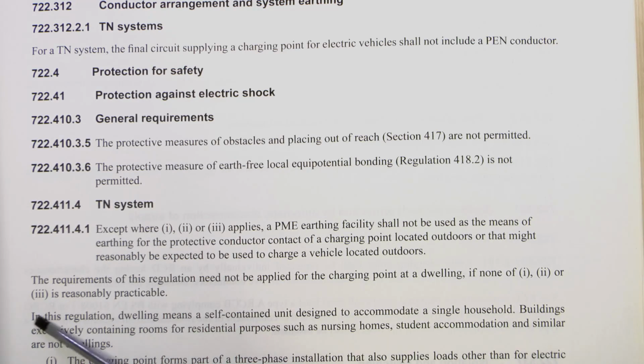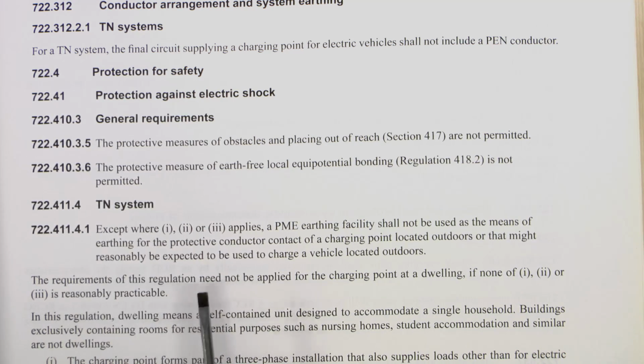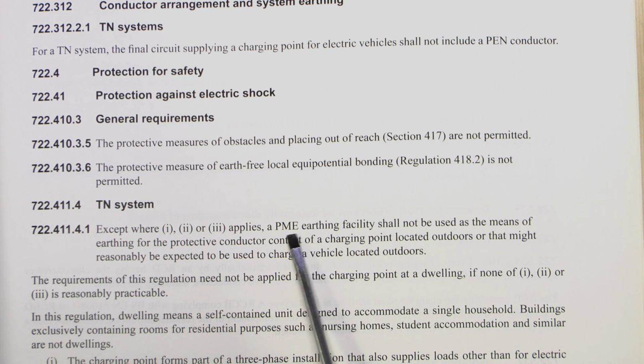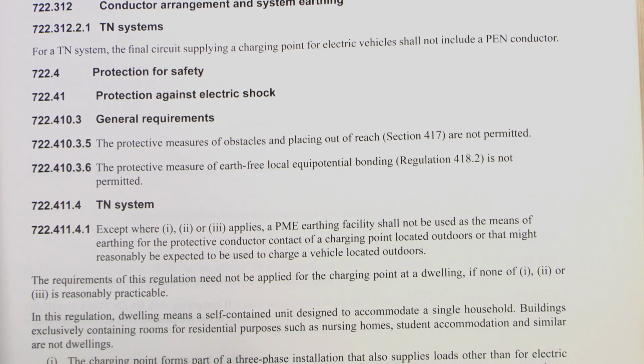What's been deleted is this bit here, which used to say the requirements of this regulation need not be applied for the charging point at a dwelling if none of 1, 2 and 3 is reasonably practicable. So previously they could be installed in a dwelling if none of those things were reasonably practicable. That's now been deleted, meaning that if you have a PME facility, which is very common in a domestic installation, then you do need to apply either 1, 2 or 3 to that. This exception has basically been removed. And there was a definition of dwelling, of course, that doesn't apply anymore because the exception has gone as well.